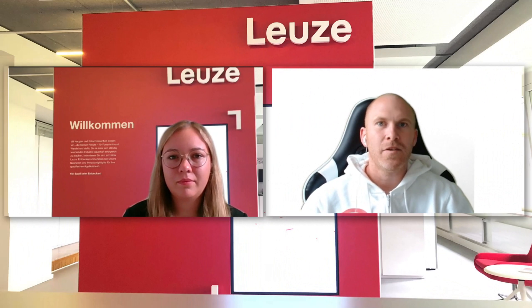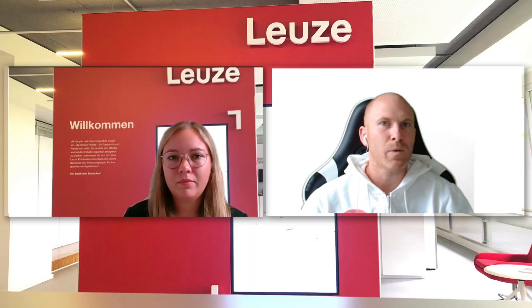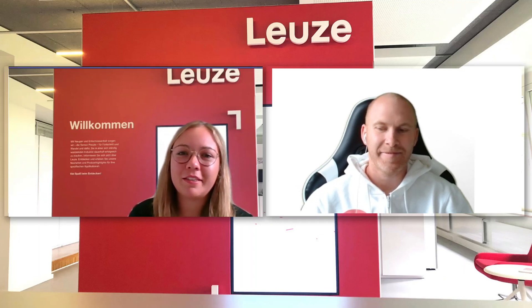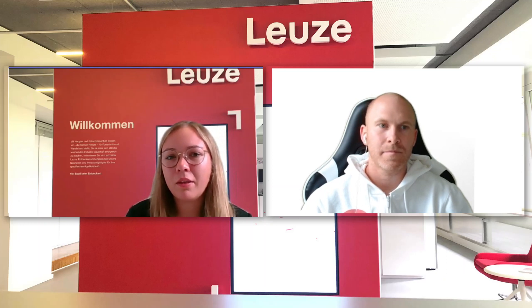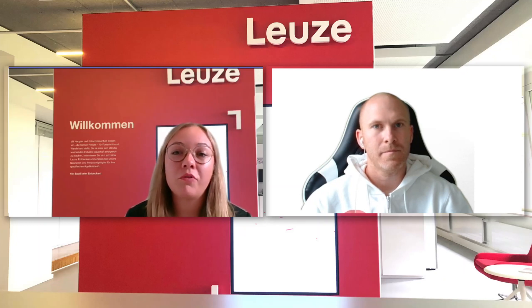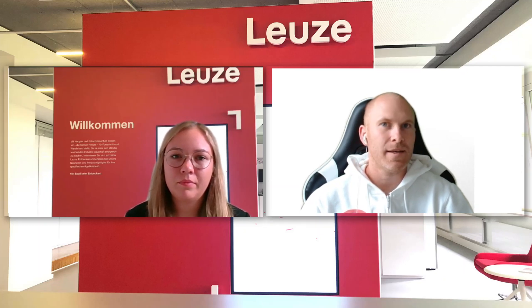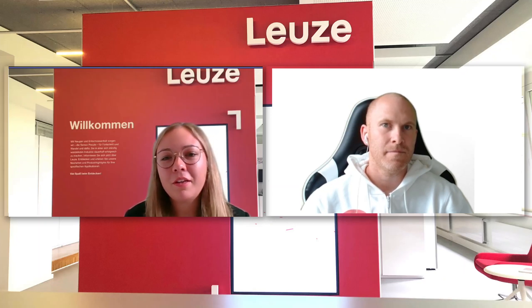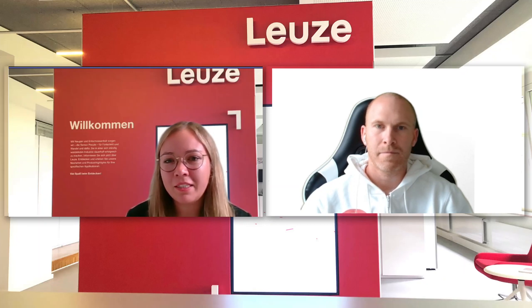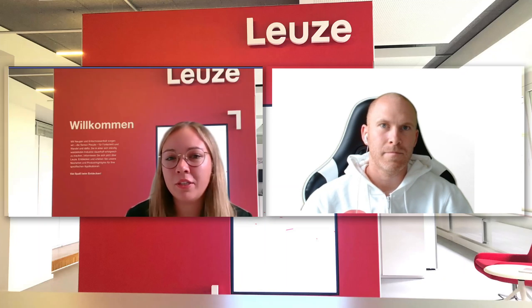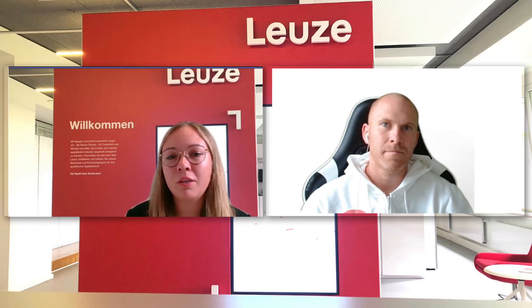Thanks, Tanita, for your presentation and the information about capacitive sensor applications. One question: what do you mean exactly by switching frequency? The switching frequency is the maximum number of switching operations per second — it indicates how many times per second the sensor switches off and on again. One additional question: is it possible to detect gas with a capacitive sensor? No. Under normal air pressure conditions, it is very difficult for the capacitive sensor to detect gases because the density of the gas is so low. As we learned, the dielectric constant of air is 1, so it has no influence on the capacity of the sensor, and therefore it won't be possible to detect gases with a normal switching capacitive sensor.